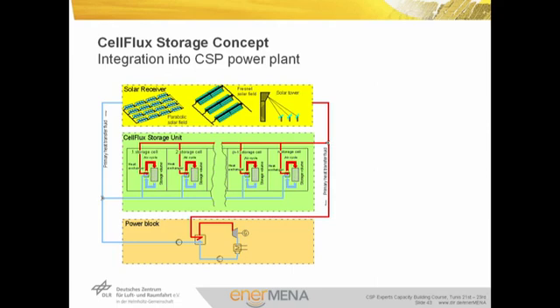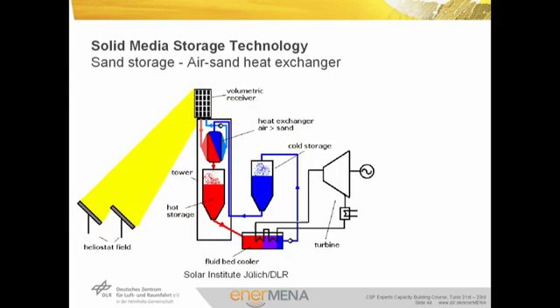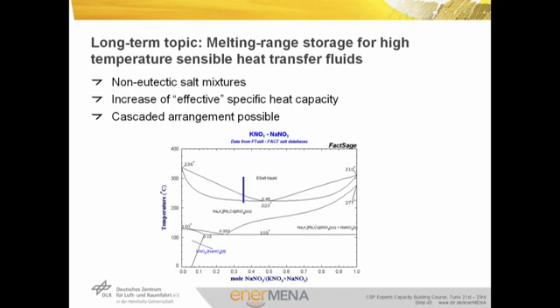The complete storage unit composed of many parallel storage cells, each including a closed air cycle, a heat exchanger, and a solid medium storage volume, is named the Cell Flux Storage Concept. This picture shows the integration of the Cell Flux Storage Concept into a CSP plant, where the storage unit is composed of various storage cells operated in parallel. Another solid media storage concept under development uses sand as storage material. Like in the two-tank molten salt storage system, the storage material is stored at two different temperatures, and the energy is transferred to the working fluid of the receiver and the power block by heat exchangers.